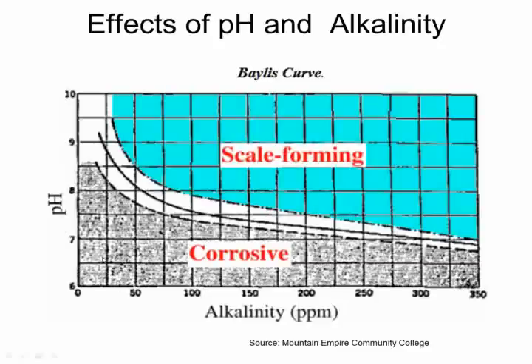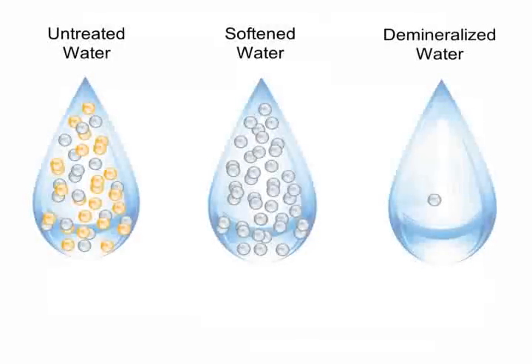And so let's say in our system, we filled up our system. Say we had some groundwater, which would maybe make the system a little bit high in pH. And let's say we had a 7.5 pH reading on our groundwater. Now, are we going to have a problem? Well, not necessarily. If our alkalinity is between 75 and 200 parts per million, we're actually still in a safe zone. So we don't necessarily have to condition this water to try to bring it into that safe zone, which is what a lot of the chemical companies do. They try to adjust your pH and your alkalinity to bring it into that safe zone, as well as add binders and things that keep things from coming into solution and going out of solution.